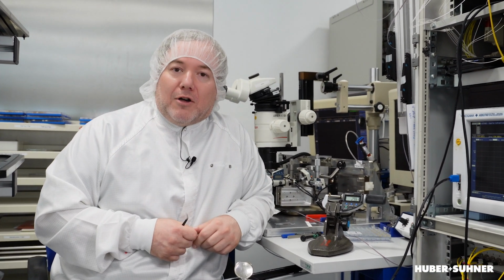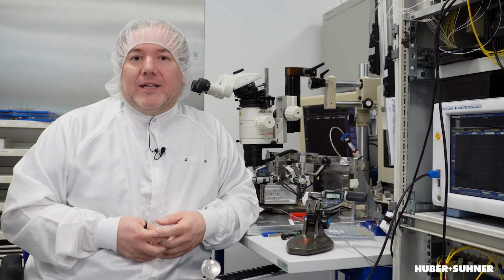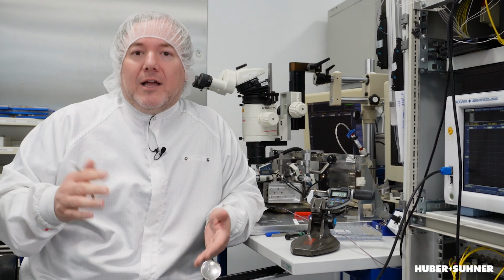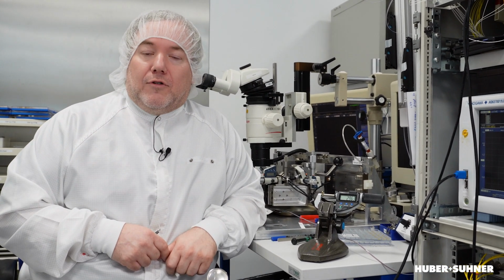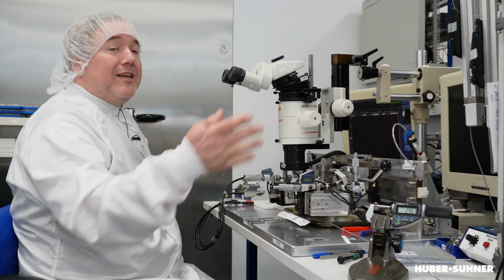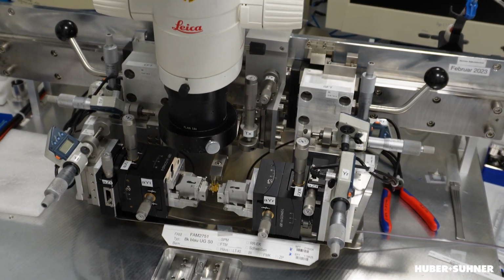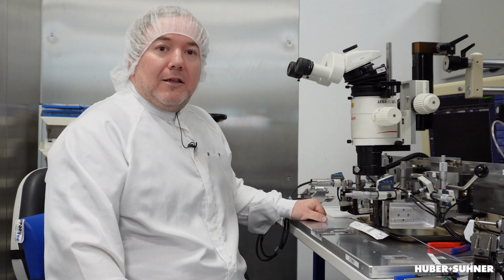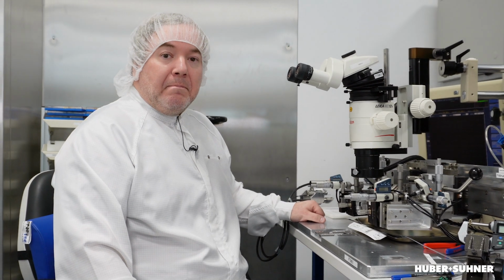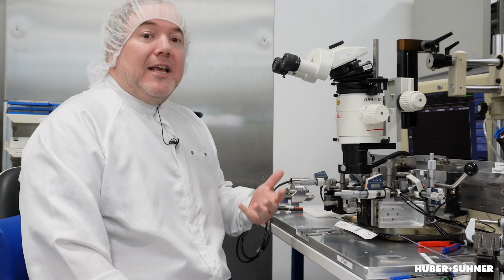If we're talking about measurement equipment which is off the shelf, like this optical spectrum analyzer, the strategy for calibration is quite simple. We send it back to the manufacturer and they do the calibration for us. The situation is a little bit different if we are talking about something like a whole assembly station. This has been designed by our own, including a lot of the measurement equipment. And so in the process of designing, we already have in mind what will be the strategy to do the calibration and maintenance in the production.